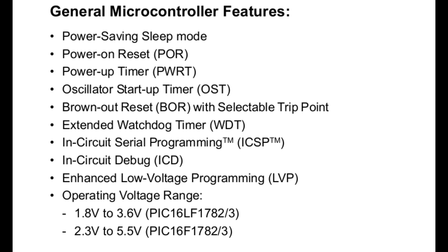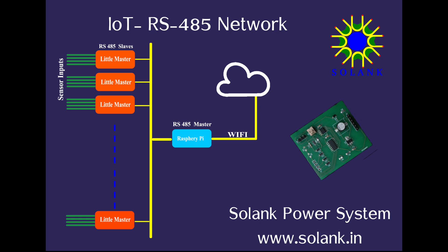And then you can do in-circuit serial programming. Only 2 pins are required for programming the controller. The voltage range is either 1.8 to 3.6 volt or 2.3 to 5.5 volt. So these are all features available with the microcontrollers. You can very easily take a sensor input and convert it into digital, or you can use a DAC to control output actuators. For example, there are motorized valves which can be operated by a 0 to 5 volt output. So you can use a microcontroller to control the water flow from fully closed at 0 to fully open at 100%, or you can regulate the flow anywhere between 0 and 100%. Such options are available through the DAC. So these are all the basic features offered by microcontrollers.